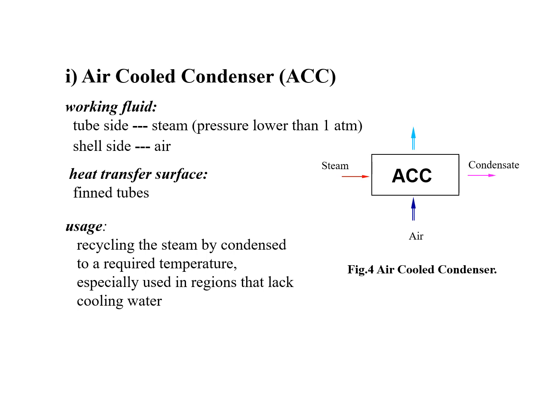Such a system is installed to recycle the steam by condensing it into liquid water, especially used in regions that lack cooling water. During the cooling process, the heat of steam is removed by air. Steam will go through a phase change into water called condensate.